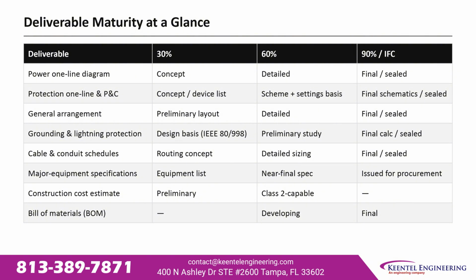The general arrangement moves from preliminary layout to detailed to sealed. Grounding and lightning protection begin with a design basis referencing IEEE 80 and IEEE 998 at 30%, become a preliminary study at 60%, and reach a final sealed calculation at IFC. Cable and conduit schedules progress from routing concept to detailed sizing to final sealed schedules.